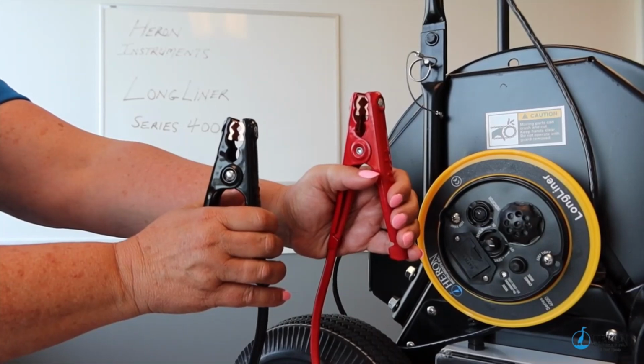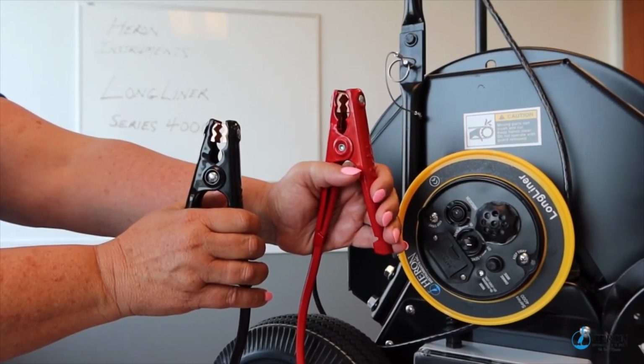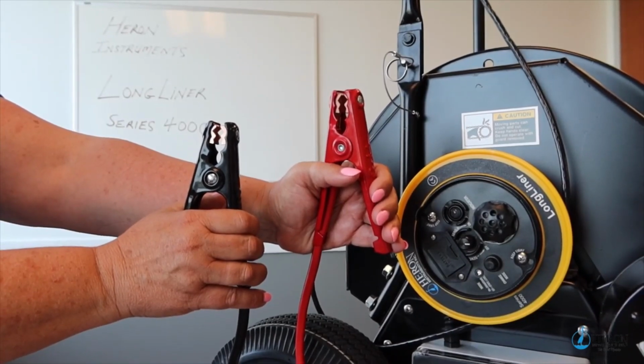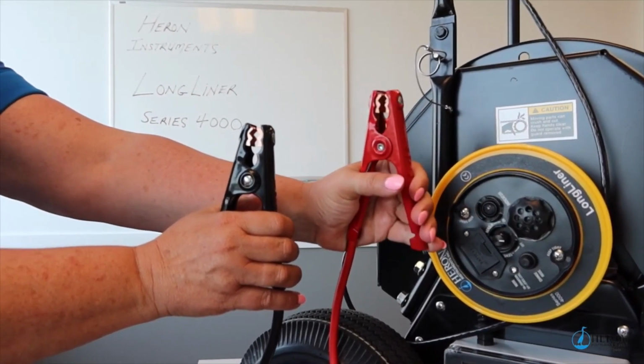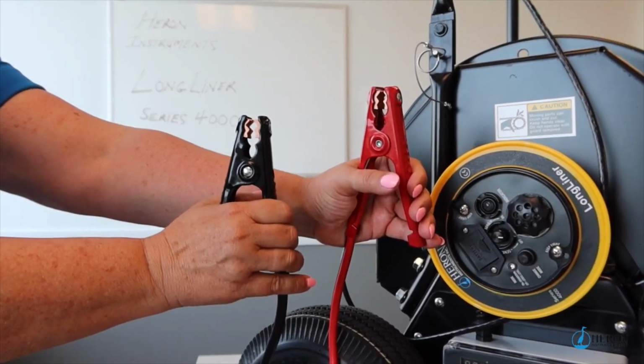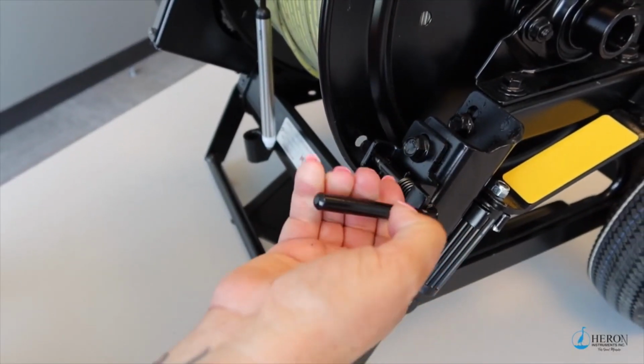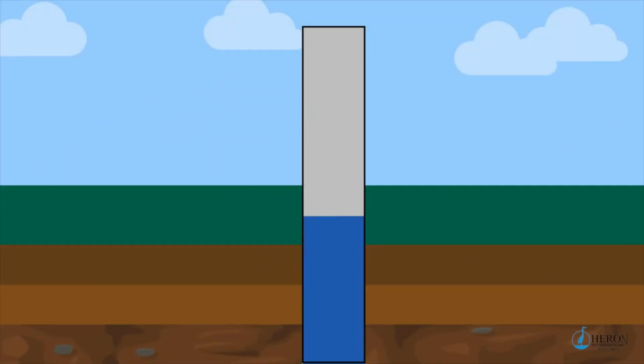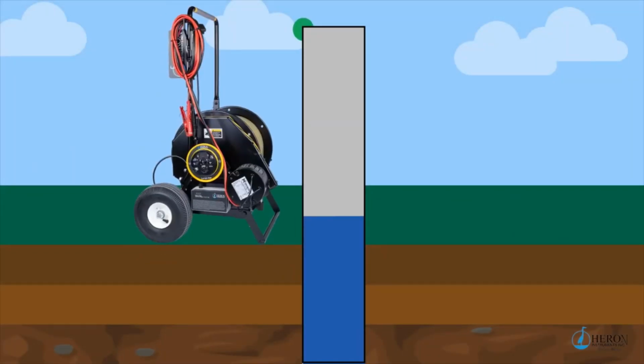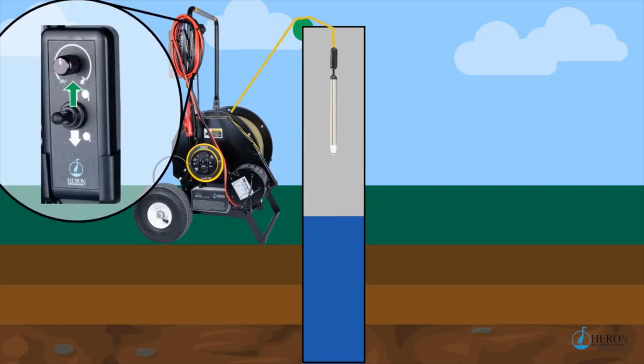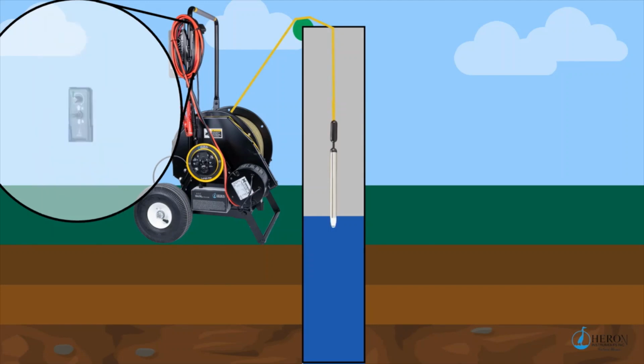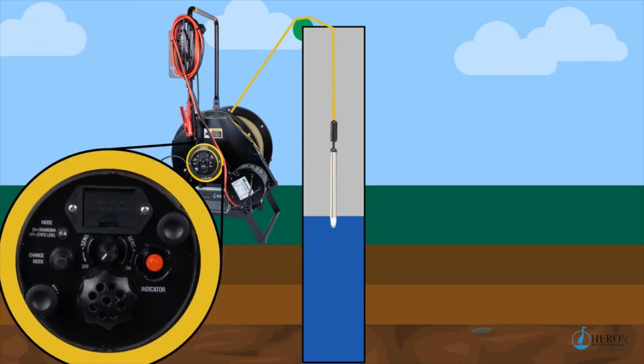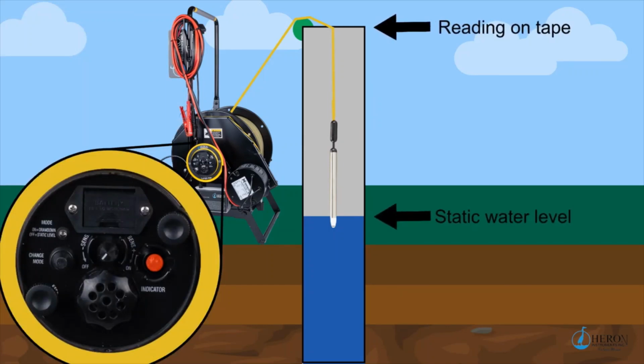Before connecting the alligator clips of the Longliner to a power supply, ensure the control switch is in the middle off position. Connect the red clip to the positive terminal and the black clip to the negative terminal. Disengage the reel brake. To protect your tape, we suggest putting a cloth over the sharp casing edge. To lower the probe in the well, push the switch to the up position. You can control the speed by adjusting the speed control knob. Clockwise is faster. The unit will start to sound on contact with the water and the LED lights will turn on. The reading on the tape will provide you with the static water level.